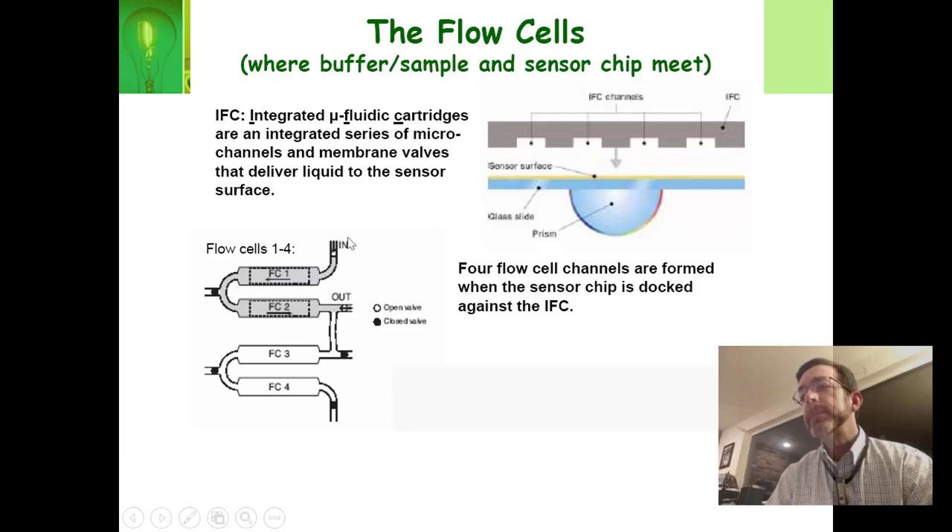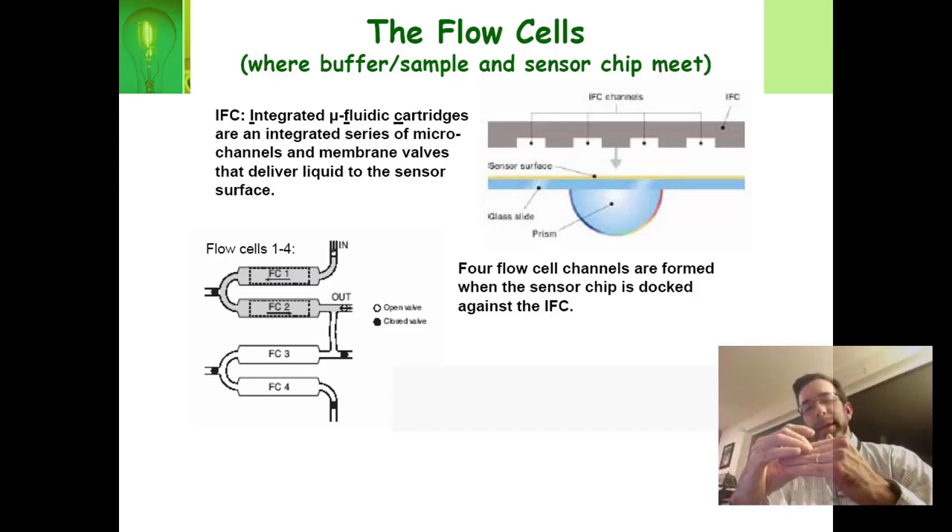Most Biacores have four flow cells, arranged in order — flow cell one, two, three, and four. You can see there are little valves represented by circles. The IFC is actually made of rubber, and air presses down on the rubber to close the valves — it's pneumatic. It opens and closes the valves depending on whether air pressure is applied. The Biacore is a pretty noisy machine because it takes air to open and close the valves.